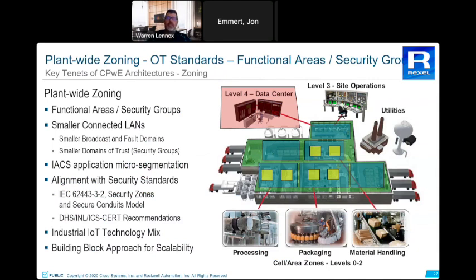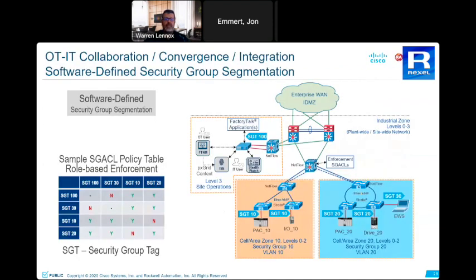And the purpose of this, we're looking at packaging, processing, and material handling. The packaging networks would require high-speed, low-latent motion characteristics. So you probably got drives with multiple axes around that area, whereas material handling could be a slower pace, and this could require long linear networks because we have conveyor operations. Or the processing, so the liquid processing, could be largely populated with instrumentation, with a large demand for highly available solutions, so redundant pathways and networks.